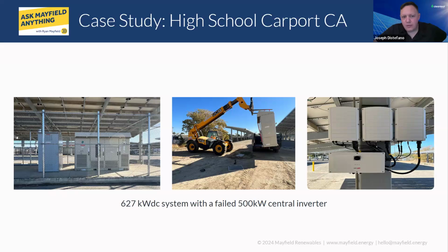Yeah, 100%. High level, this was a 1 megawatt project with two 500 kW central SatCon inverters. We had one fail, a catastrophic failure, unsalvageable at that point. We worked with the client for about a year trying to come up with a design. We reached out to Ryan and his team, and Ryan got us a good set of drawings and a good design for half the system repower. This was a pretty interesting project, falling under the DSA in California. We had to resubmit a whole set of drawings and go through the whole approval process again for about a year before kicking off the project.